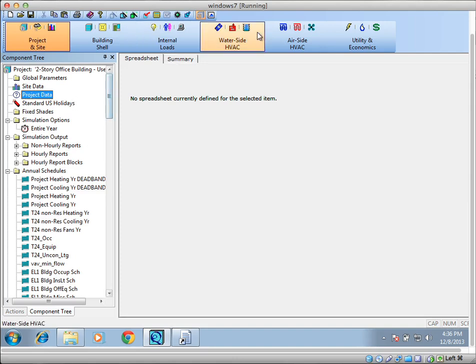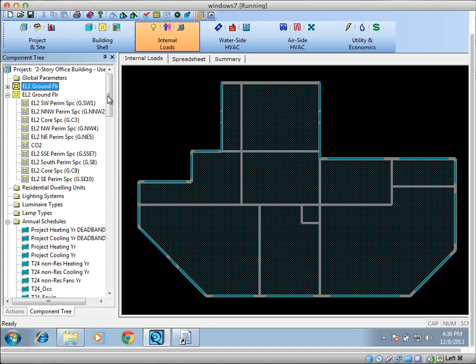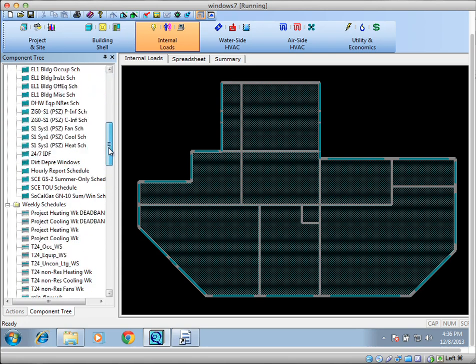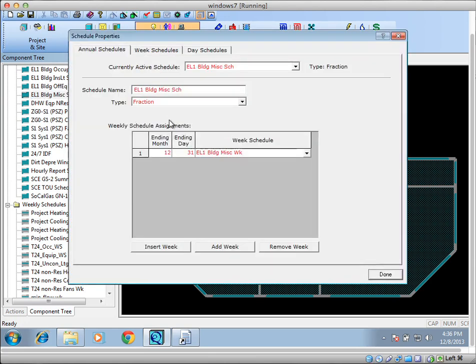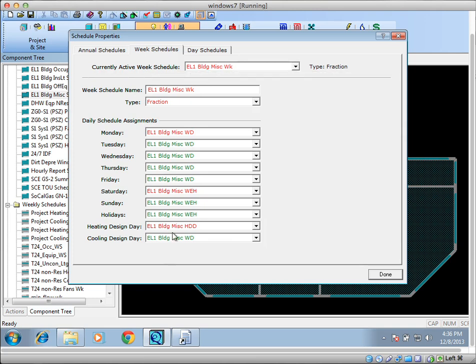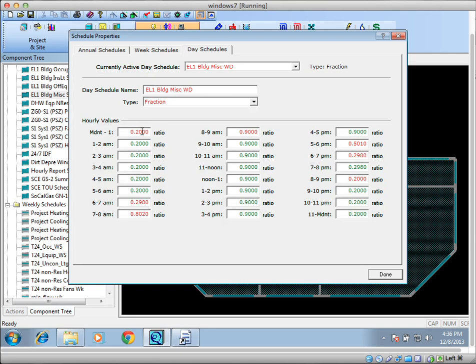But design days are there. And design days even have relationships to schedules. The last thing I'll show you really quick. But if you were to look at any schedule, such as miscellaneous schedule, this is the equipment schedule. It's usually the week tab. So here's the annual schedule. If you go to the weeks tab down here, you can actually see there is a unique pointer for the heating design day and the cooling design day. So here's where you could actually, if you wanted to, create a unique schedule for the electrical equipment in the building. Right now it just sets the weekday schedule, which looks like this, where you see it starts at 20% and peaks at 90%.